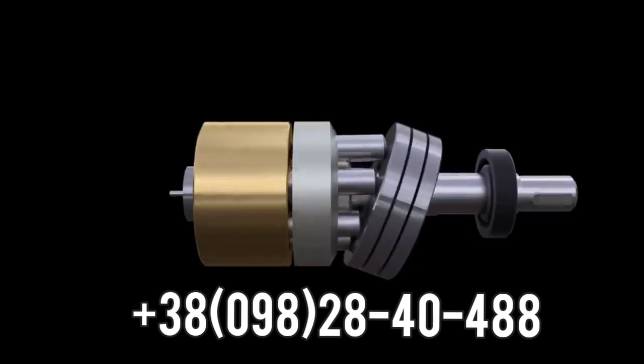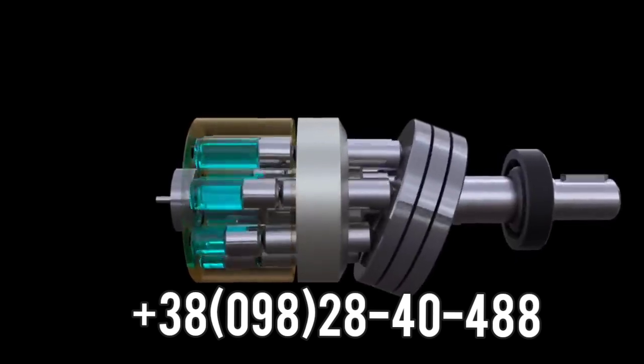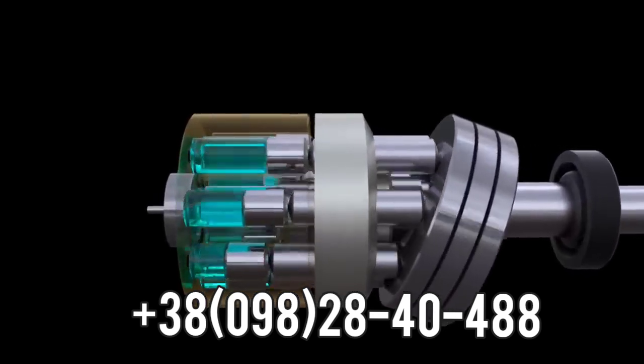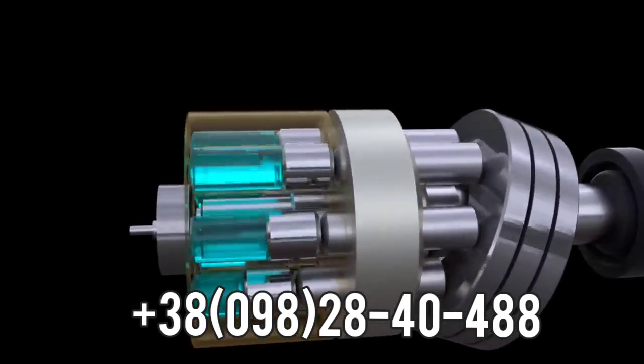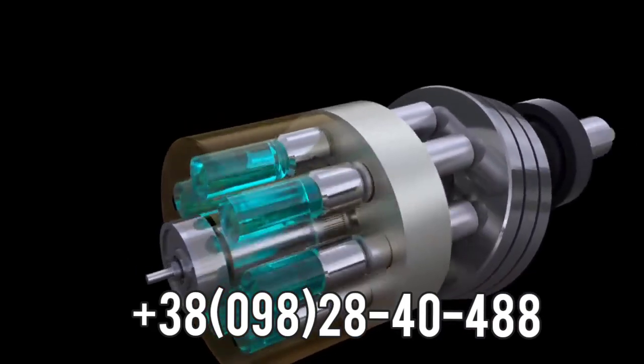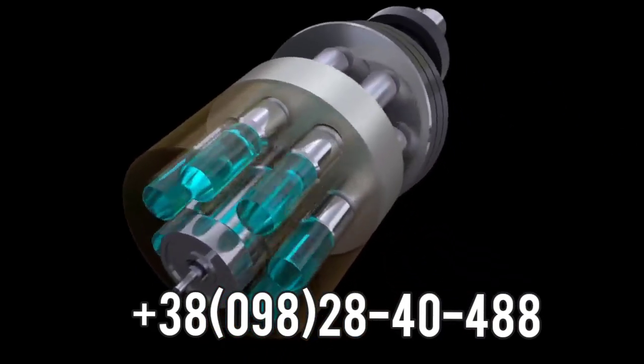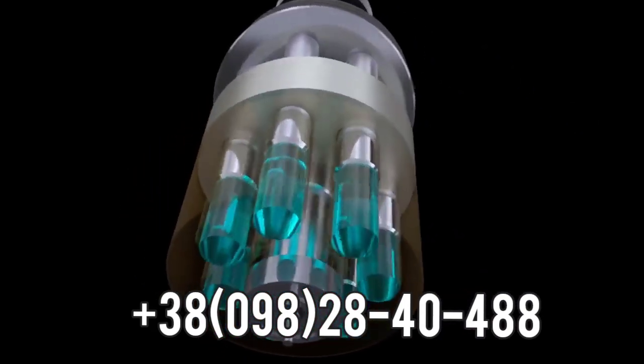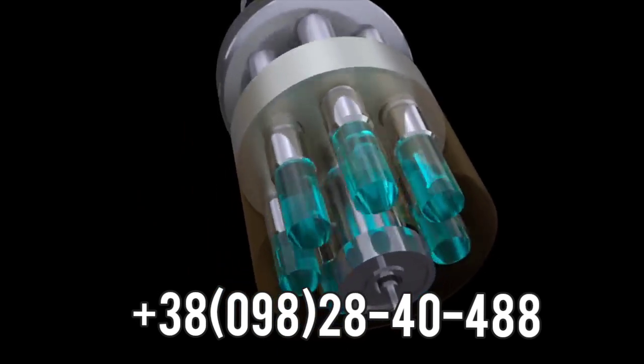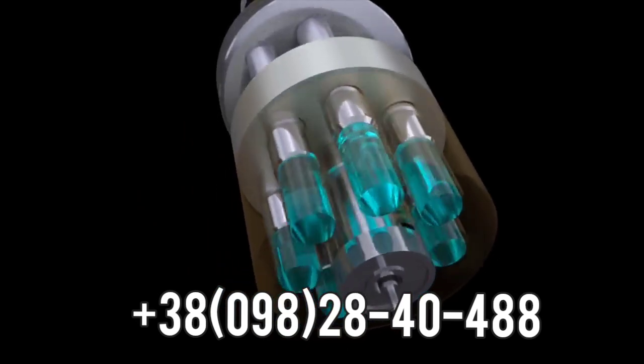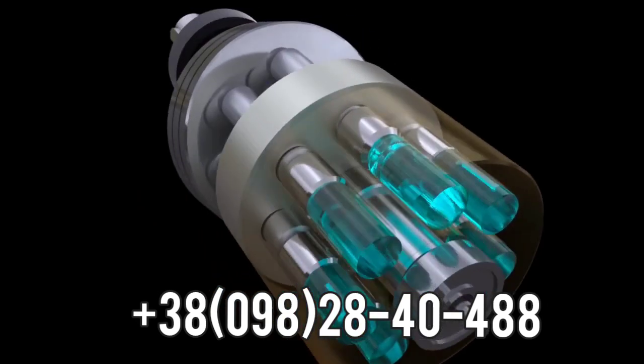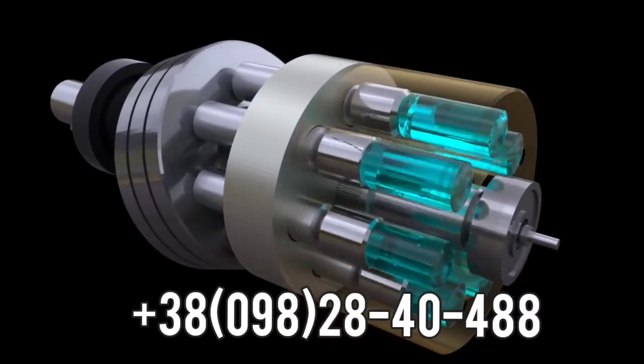At the moment when the pistons move increasing the volume of the chamber, they are connected to the suction line. And when the pistons move in the opposite direction, thus reducing the volume of the working chamber, they are connected to the discharge channel. The pumping capacity of an axial piston pump is determined by the number and diameter of its pistons, the space between them in the block, as well as their stroke.